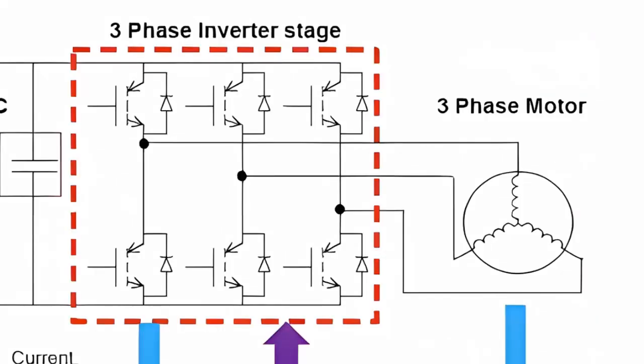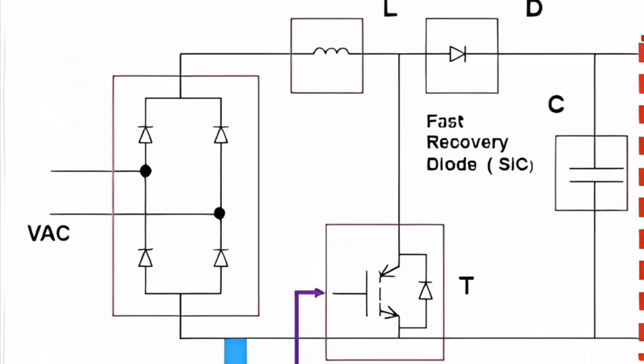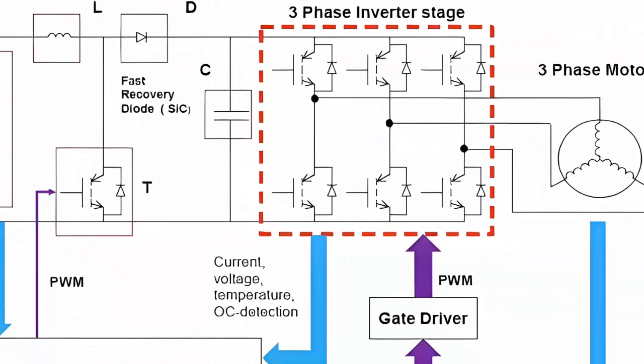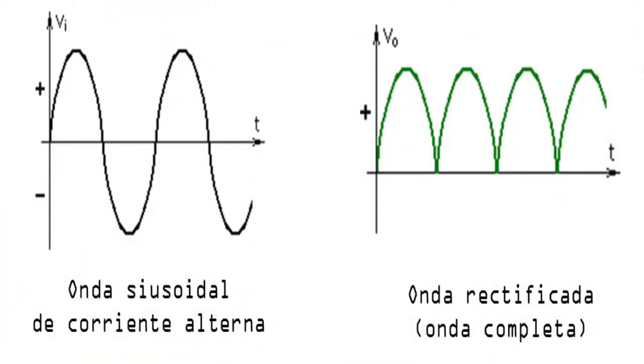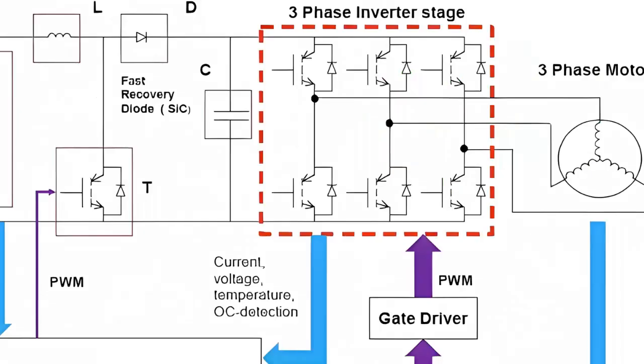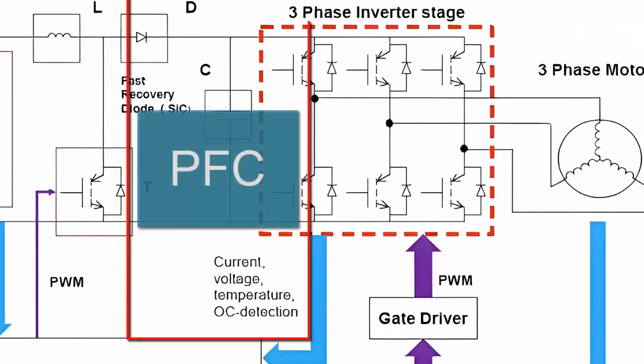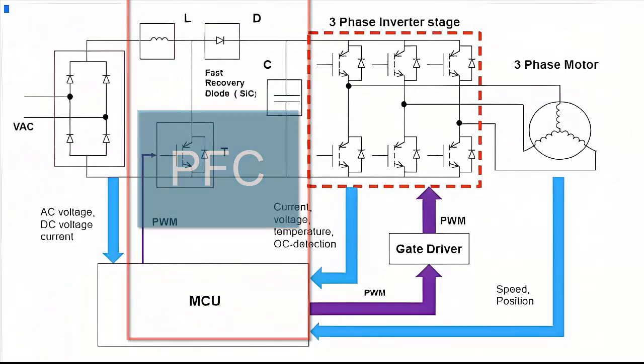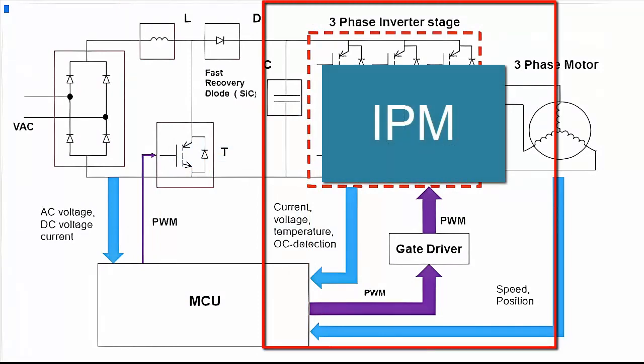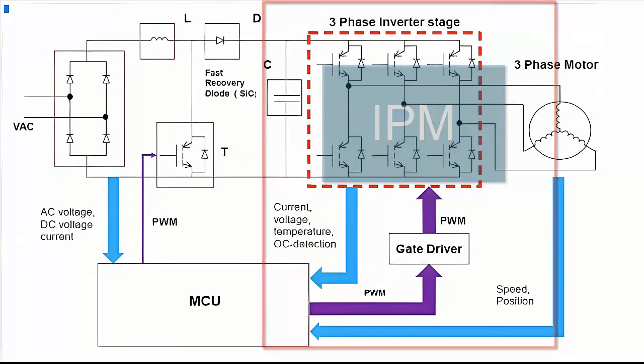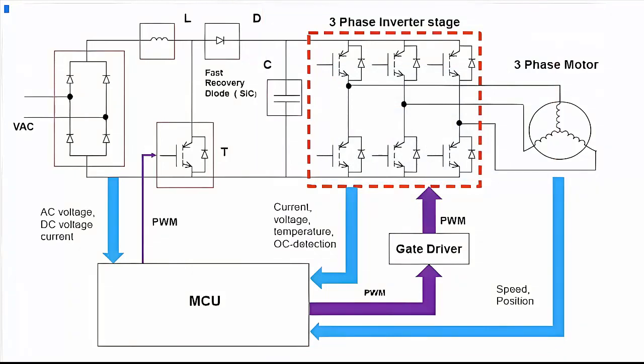To improve the efficiency of the equipment, the air conditioner compressor is of the 3-phase alternating type. Since the current feeding the equipment is of the monophasic alternating type, a transformation is required starting with rectification. Then, the PFC circuit controls the voltage, followed by the IPM circuit, which distributes the current to the 3 compressor coils through 6 transistors, generating a highly efficient 3-phase alternating current.